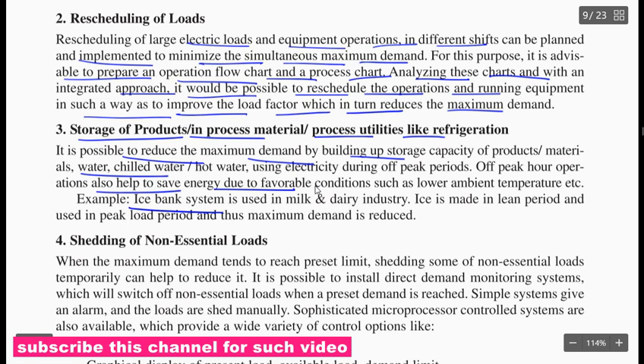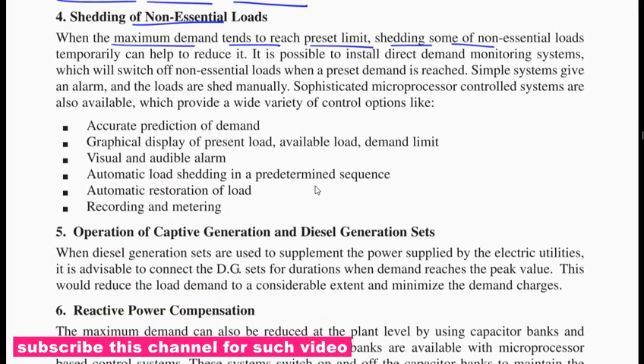Ice bank system is used in the milk and dairy industry. Ice is made in the lean period and used in the peak load period, and maximum demand is reduced. Shedding of non-essential load: when the maximum demand tends to reach preset limits, shedding down some of the non-essential load temporarily can help to reduce it.